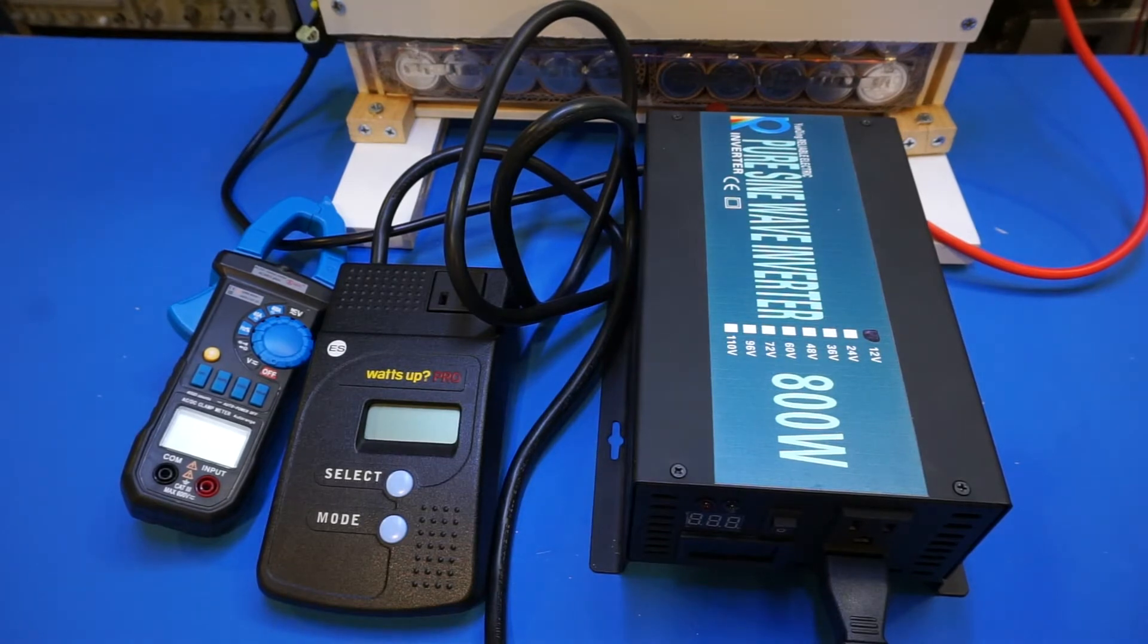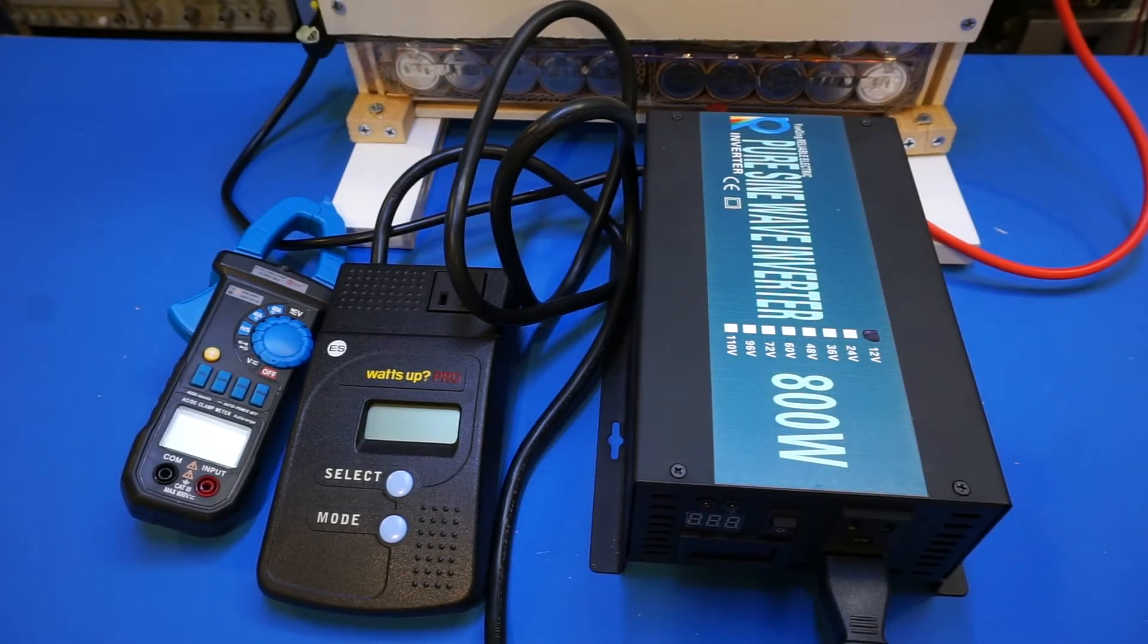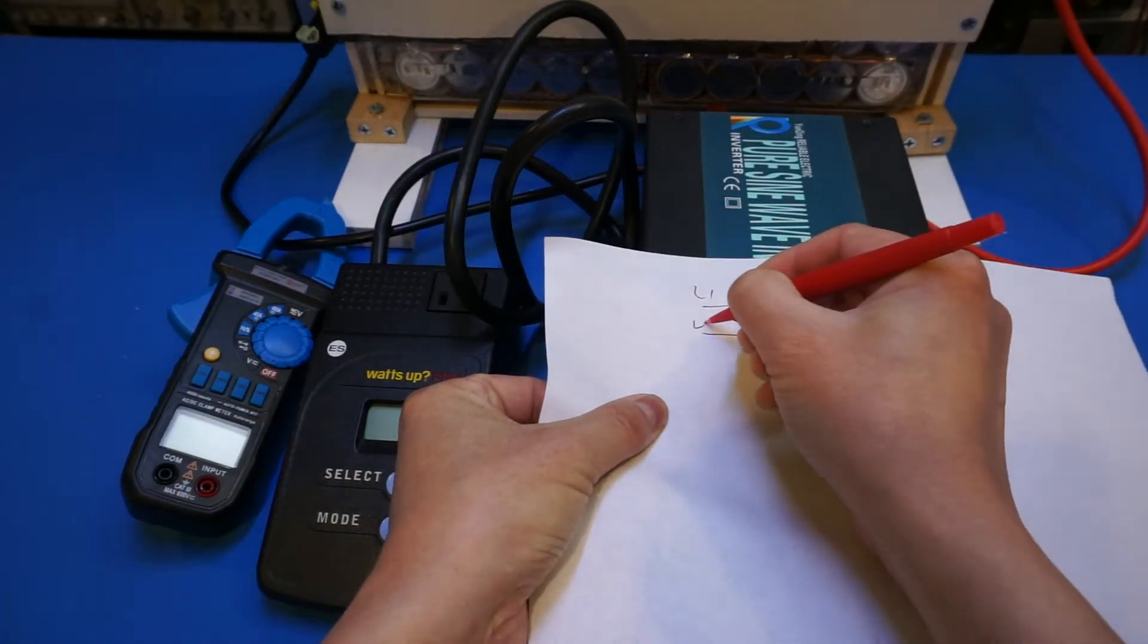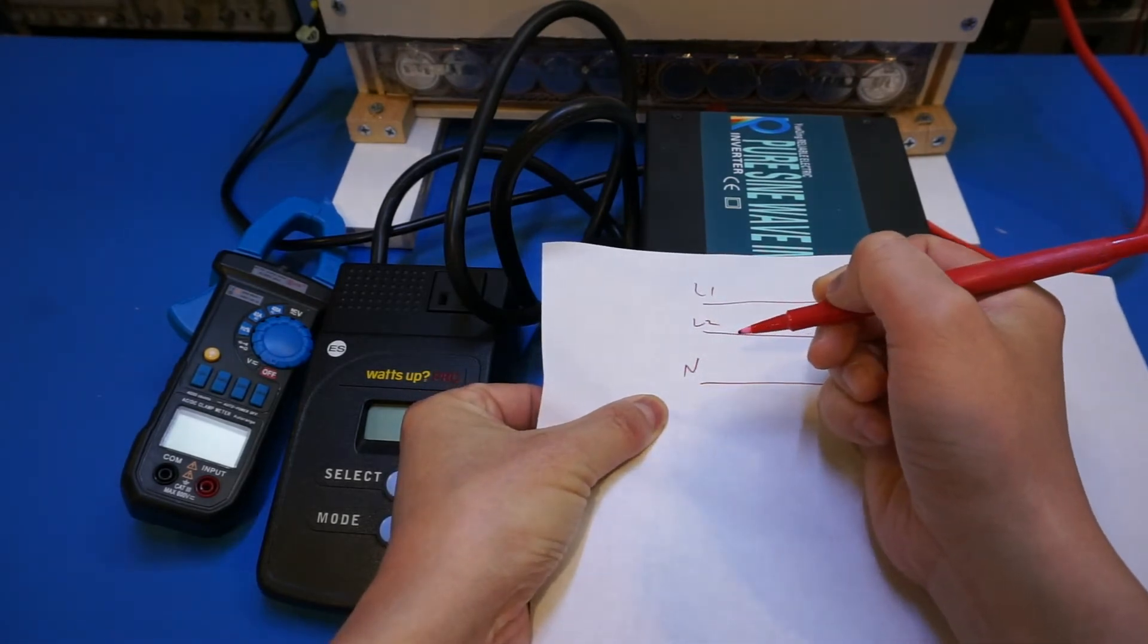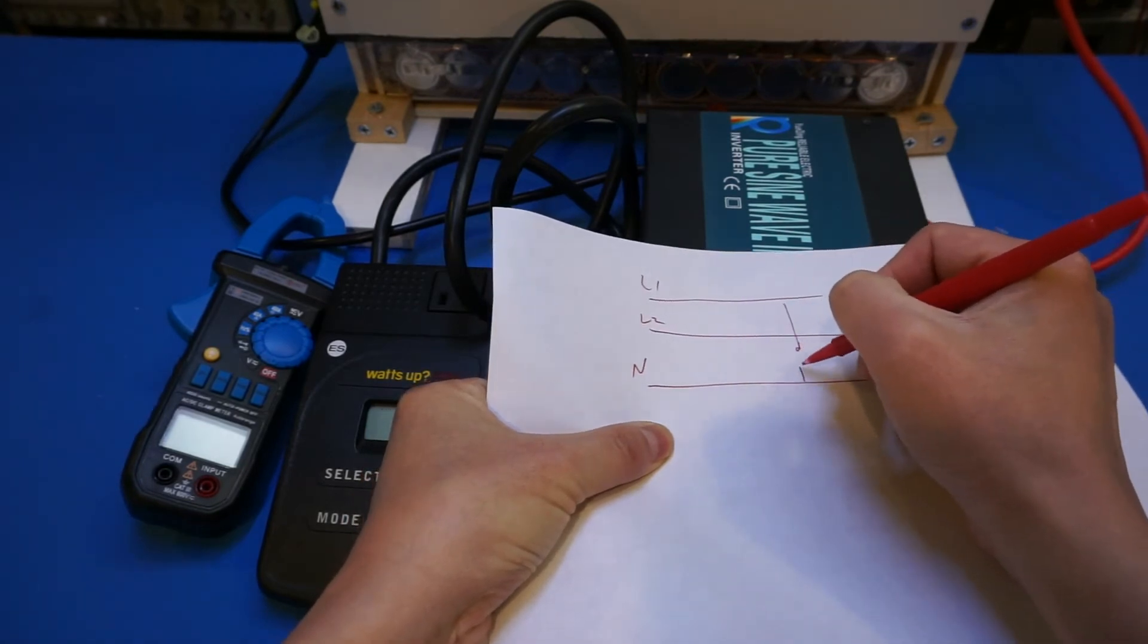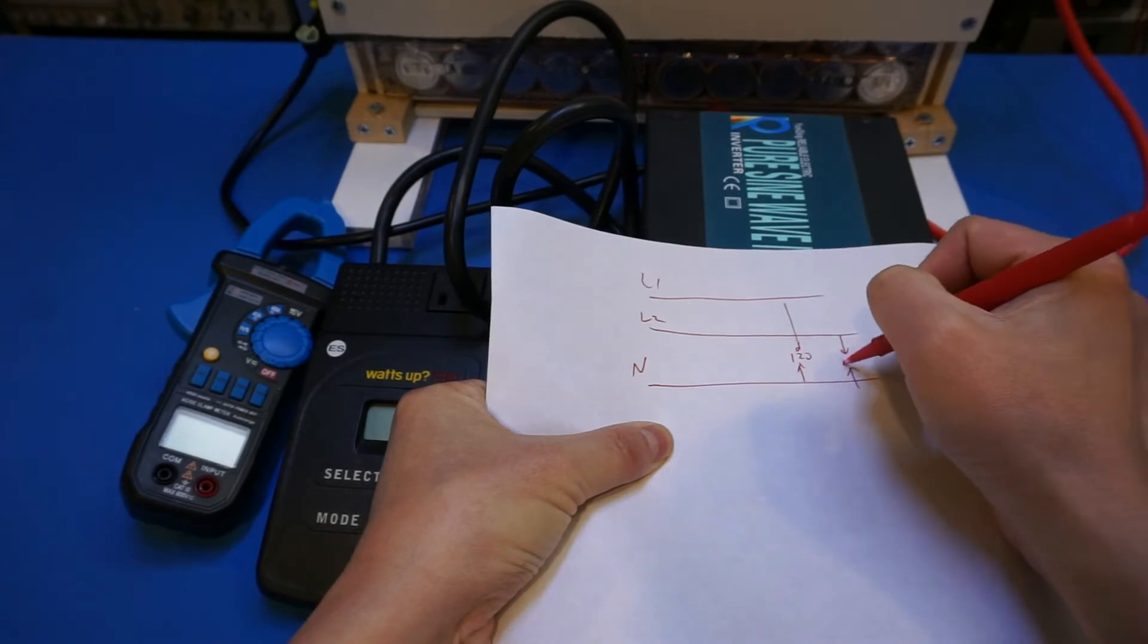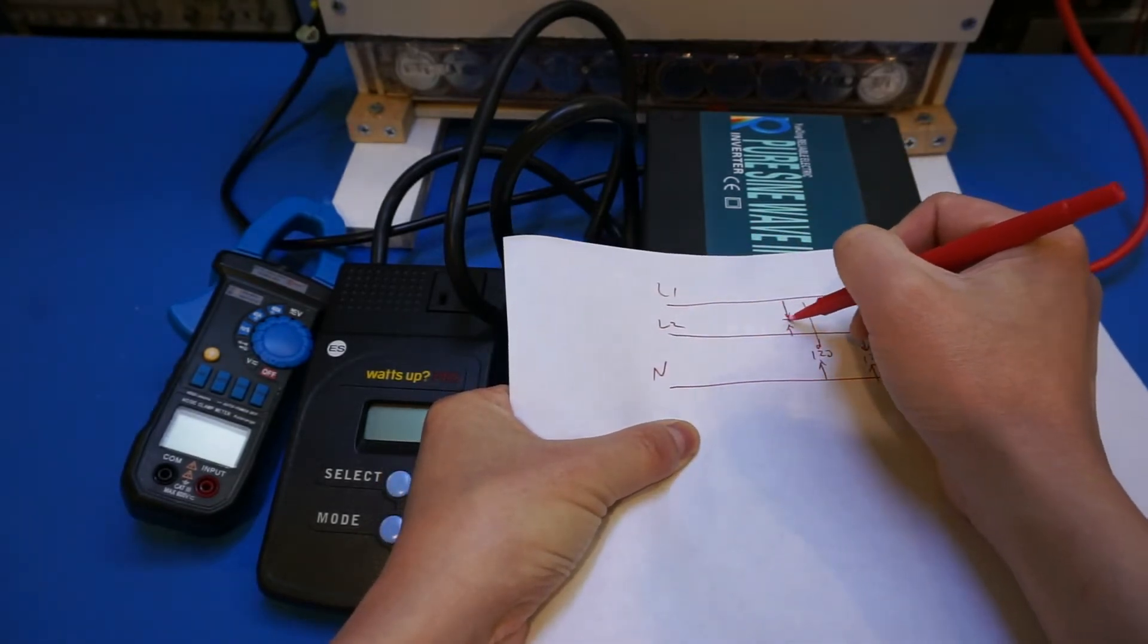Well, the main circuit coming into each house in the US uses a so-called split phase scheme. So basically it has a neutral line and two live lines. So let me draw that just here. So you have the live one, live two, and the neutral. And each wire is basically 120 volts with respect to your neutral, 120 and 120. But between these two lines, we have 240.